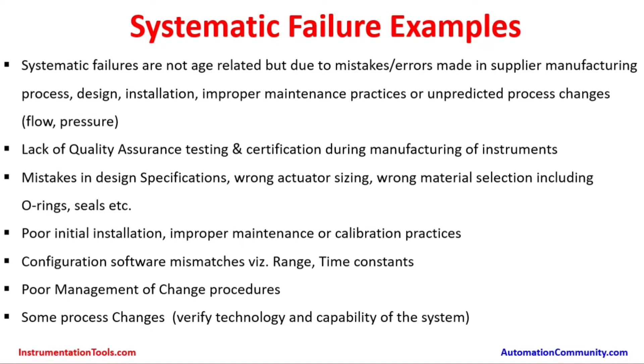Other causes include lack of quality assurance testing and certification during manufacturing, mistakes in design specifications, wrong actuator sizing, and wrong material selection including o-ring seals. O-ring seals are very critical and minute components situated in different parts of the actuator and are impacted by environmental conditions such as temperature and dust. Different o-ring materials have different temperature capabilities, so using a material in a higher-temperature environment than it is rated for makes it prone to fail. The type of materials used must be evaluated before selecting seals or o-rings.